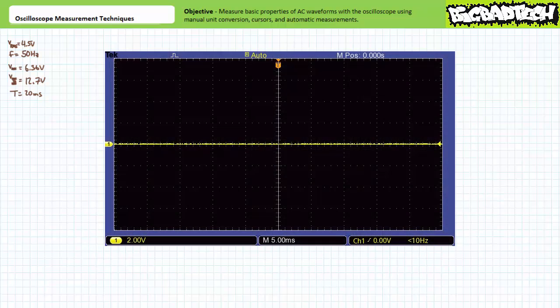Given we anticipate a 6.4 volt peak value and our display includes 8 divisions, top to bottom, a vertical sensitivity of 2 volts per division might do the trick. Given this sensitivity, we should anticipate the waveform to peak slightly more than 3 divisions above and below the horizontal axis.